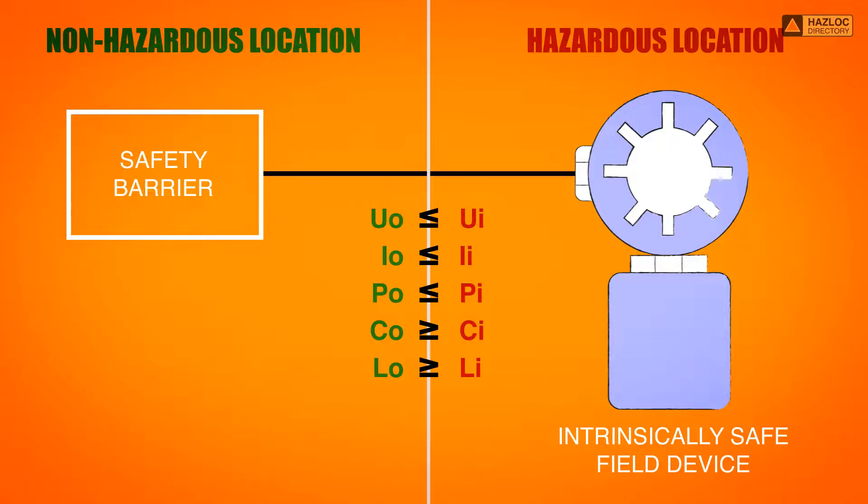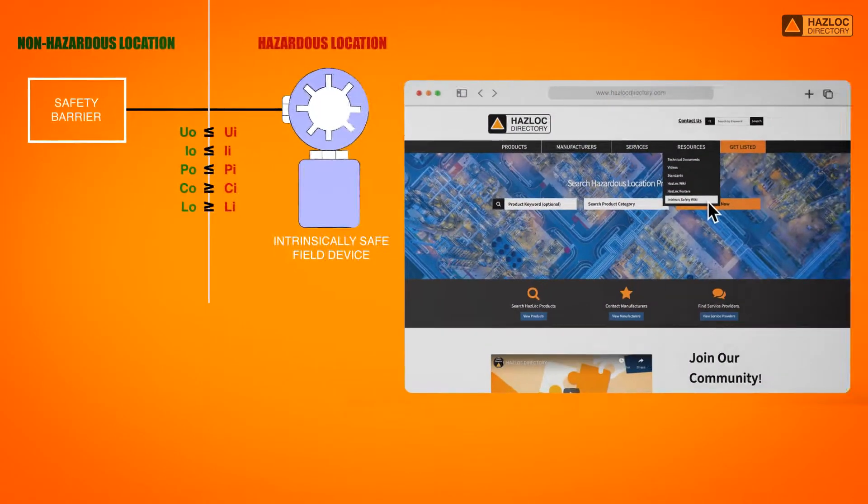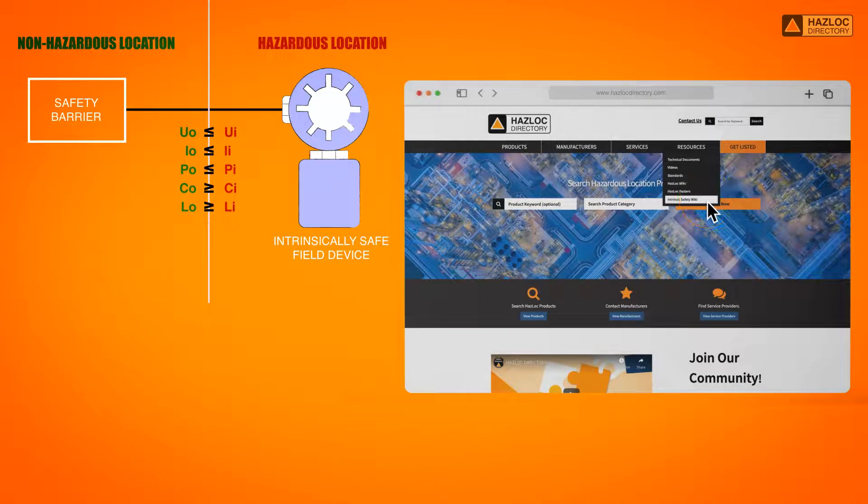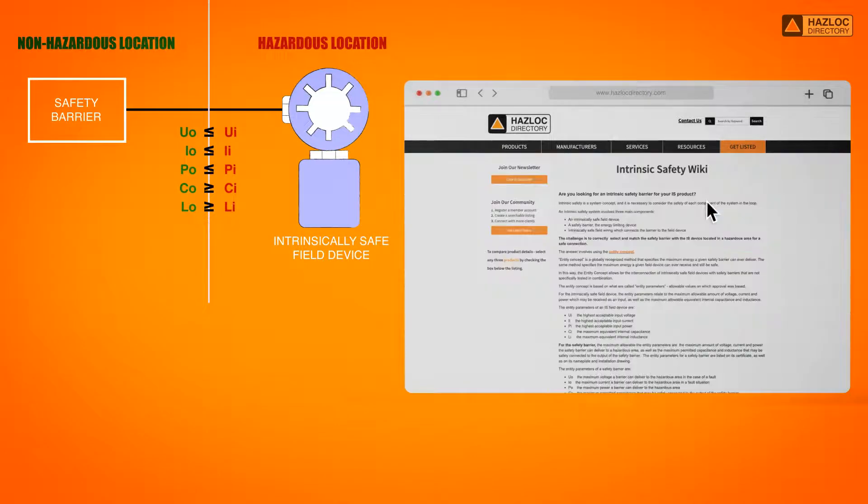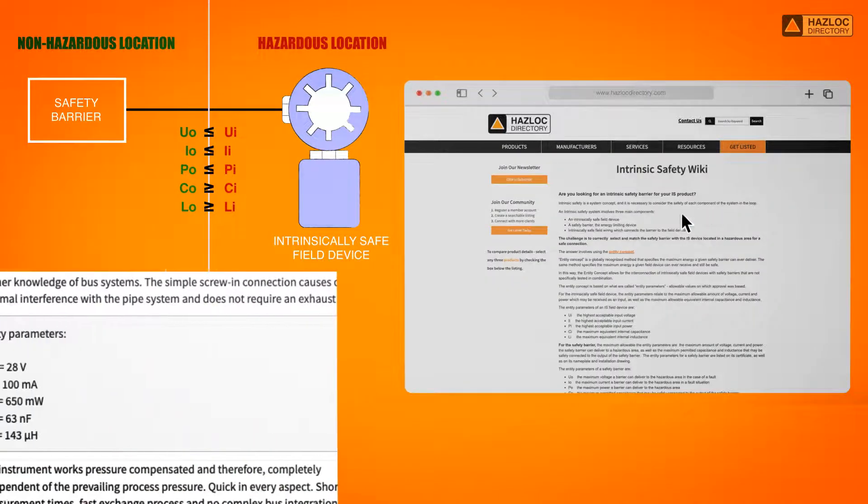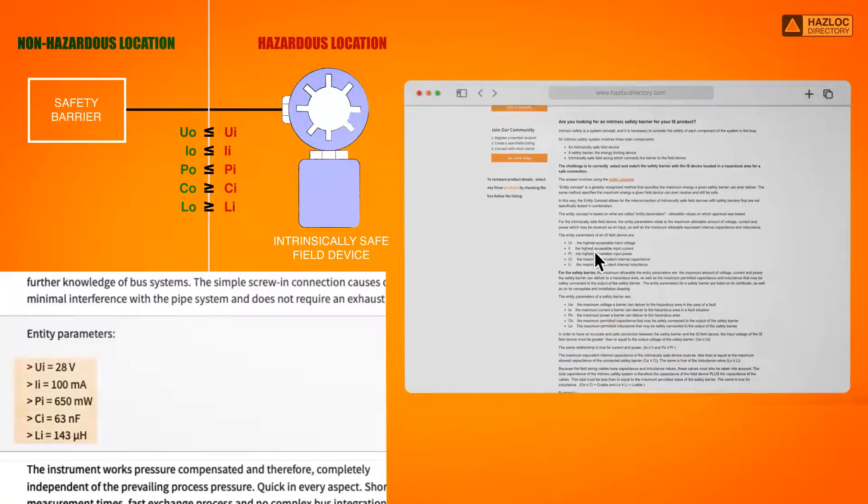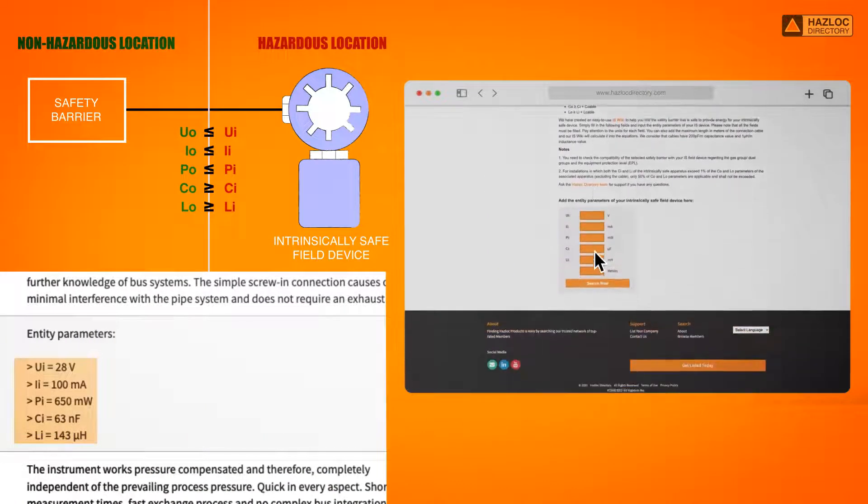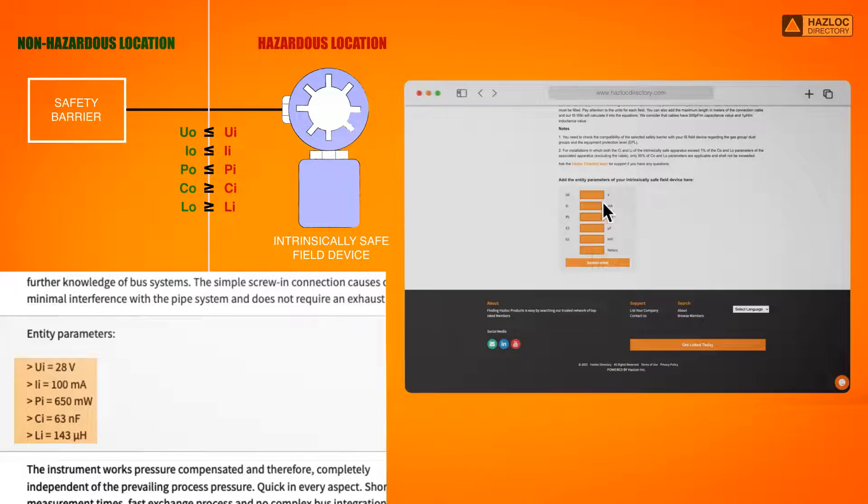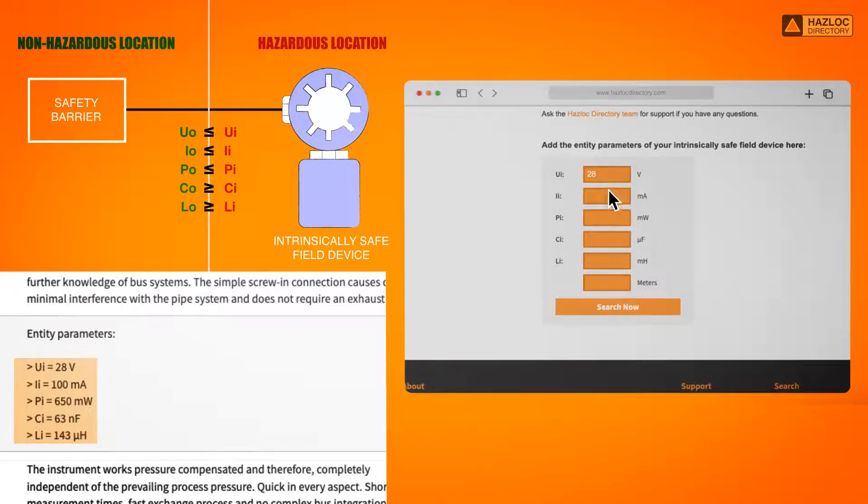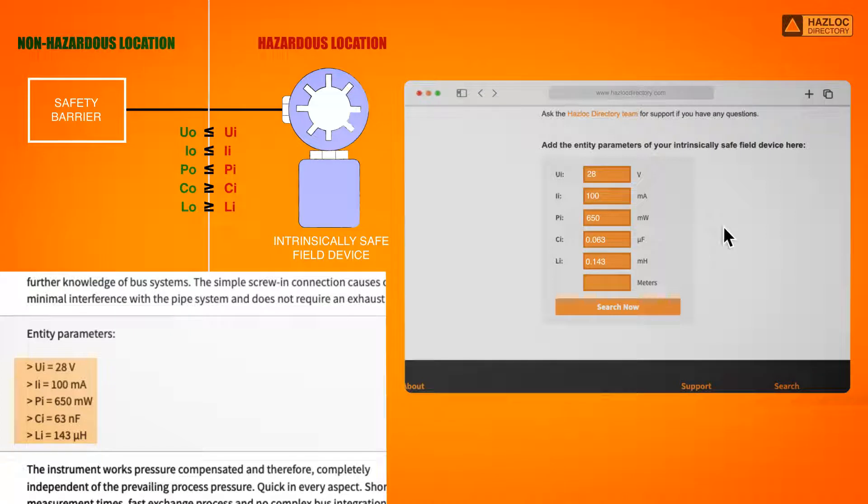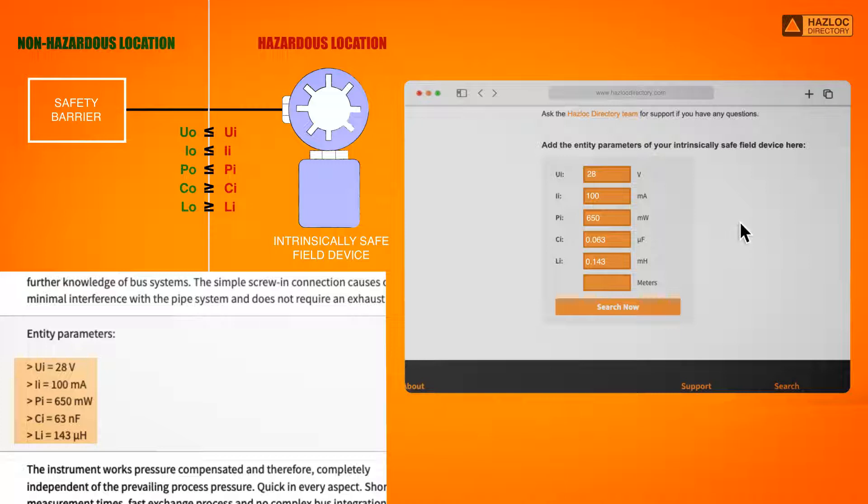To find a safety barrier that can make an intrinsically safe system with this gas quality measurement device, we input the entity parameters of the IS device in the fields provided in the intrinsic safety wiki. Also, we need to add the length of cable that is required to connect the safety barrier and the IS device. In our example, we assume the connection cable is 30 meters long.